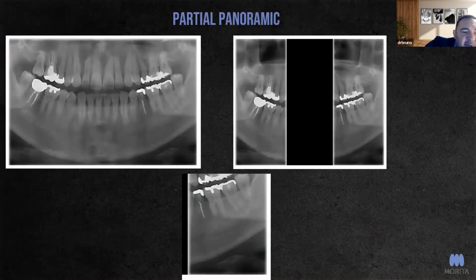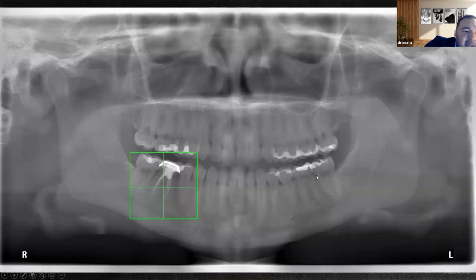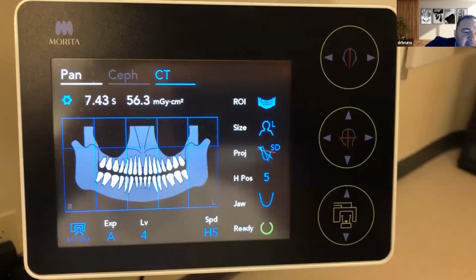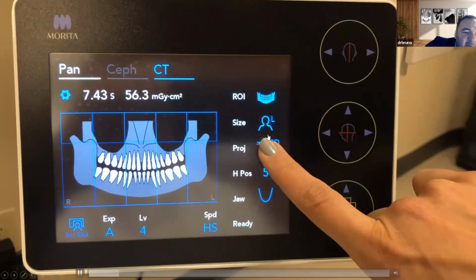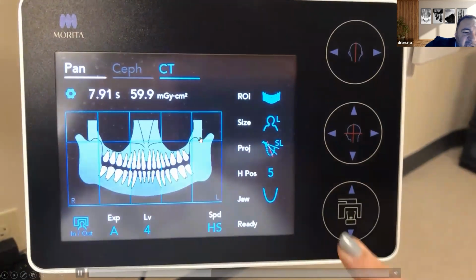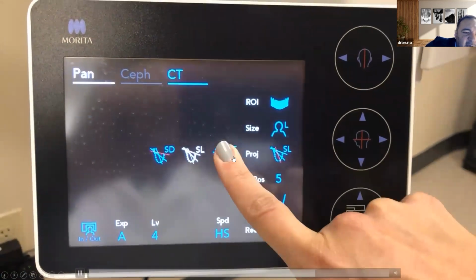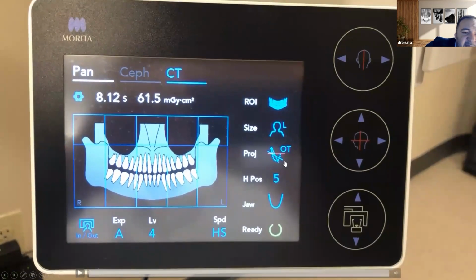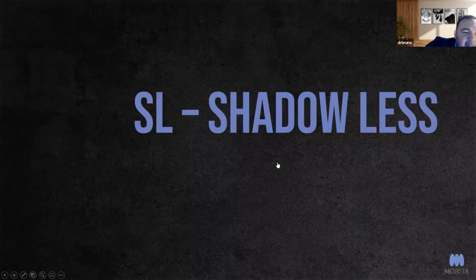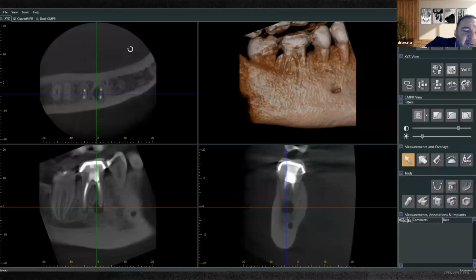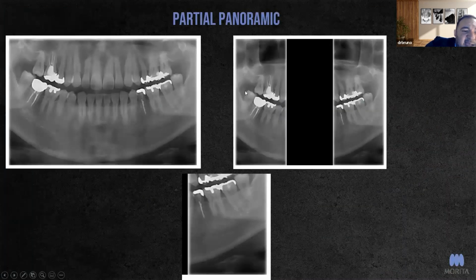For those who use the R100 or also the X800, it's important to remember that you also have the ability to crop panoramic images. If you want to do the panoramic bite wings, and that would be back here, one very fast, and that would be this module here, where you can go to normal, to shadow less, and then you have the orthogonal projection, which is the OT. So the OT you would use to do the bite wings, panoramic bite wings. That's when you do the OT. And then if you go back here to your panels, you just unselect the condylar heads and the central incisors, and you select the OT. This will be equivalent to what's called a panoramic bite wing with your Morita X800.